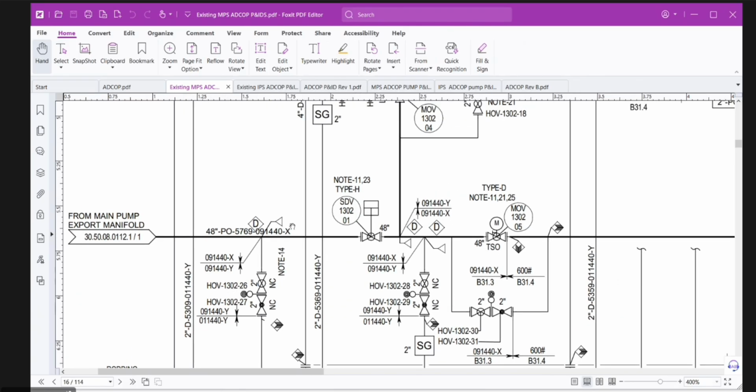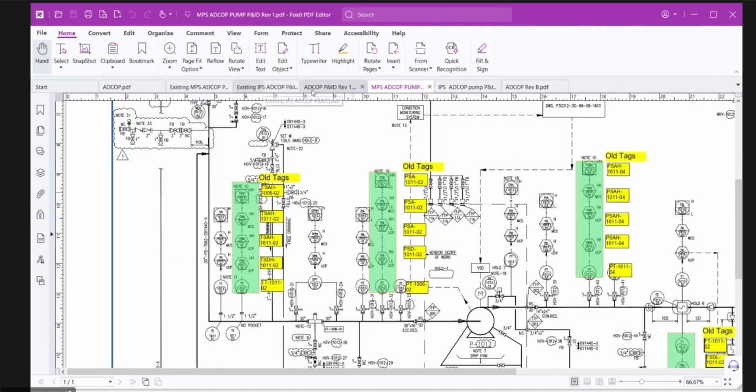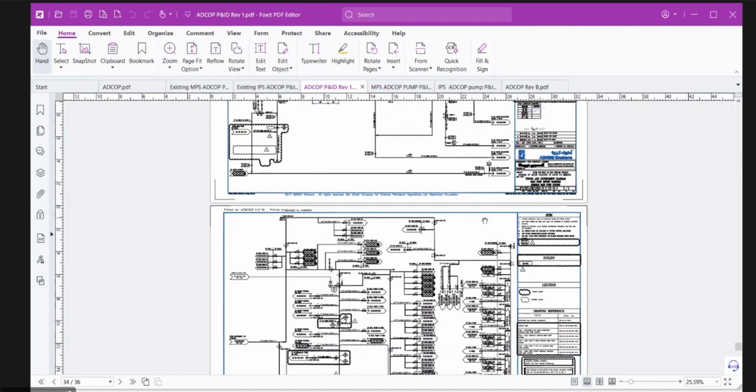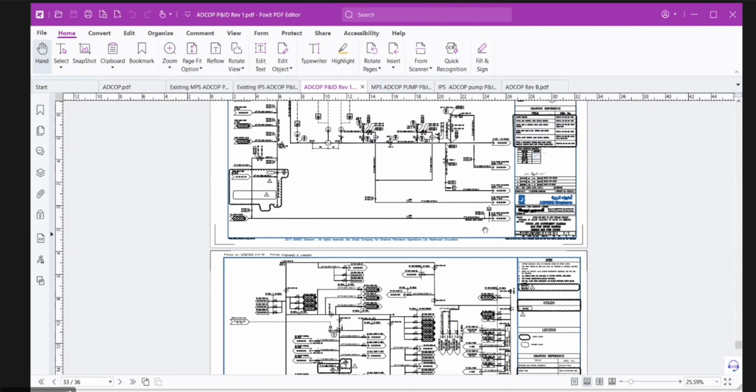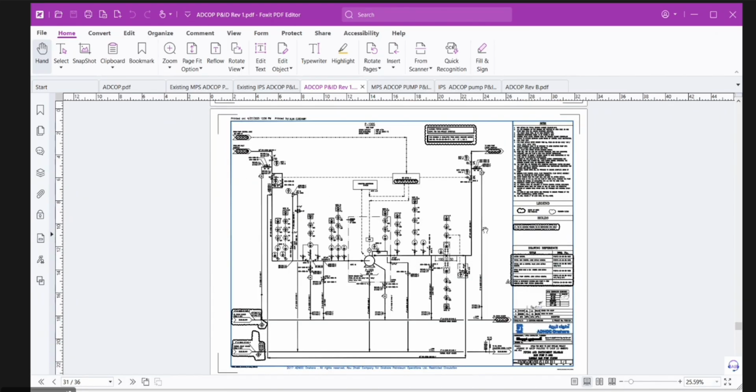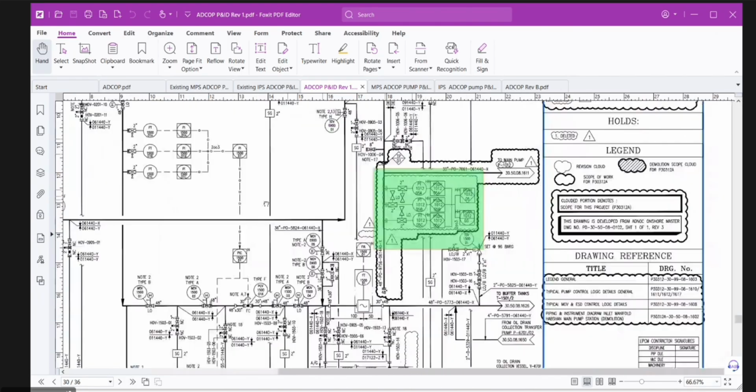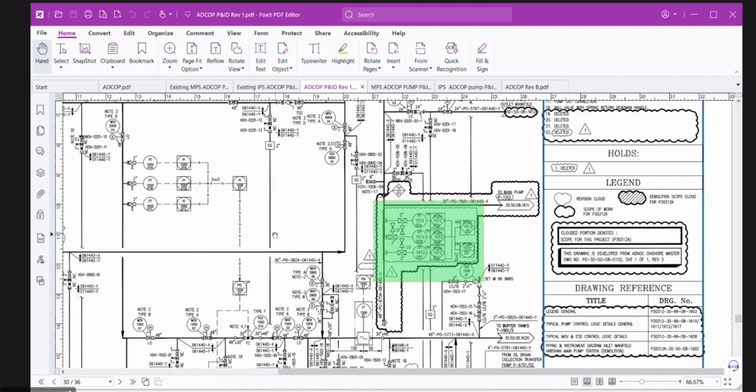Okay guys, please bear with me. I just want to refresh it. On 70% flow, it will trip the entire system, ESD2. And on high pressure on an individual pump, this will trip the individual pump. So these are two independent functions and independent safeguards. So I have taken credit of SIS1 for this case also, considering that this is SIL2. Now again, this is the last opportunity for me to convince you. Do you still agree that the operator is going to be there more than 10% of the time?